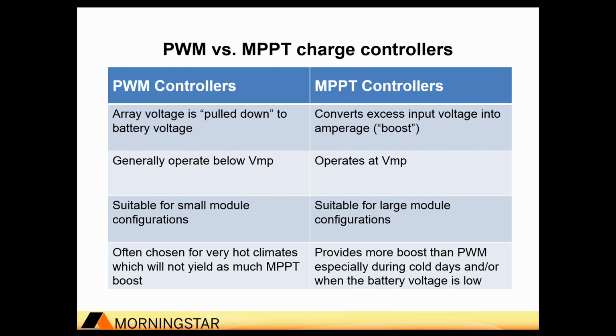Real quickly, just to wrap up on the controller section, I wanted to mention a couple of points on PWM versus MPPT controllers. In hazardous locations, we require the Class 1 Div 2 rating, and that limits us to the PWM side of this chart. But if it's outside the zone where that hazardous location rating isn't required, you can consider MPPT controllers. There are some benefits to doing so.